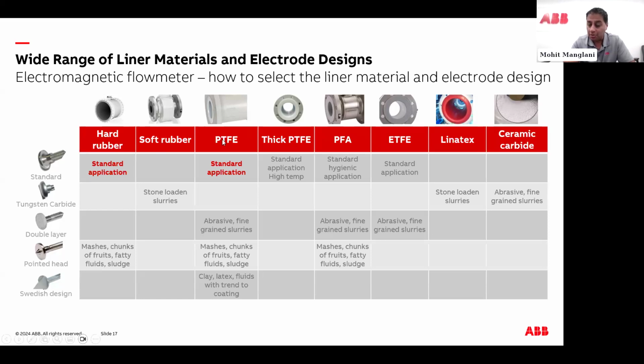You have Teflon. This is great for chemical applications, upstream, and oil and gas applications. Thick Teflon, which is basically Teflon but thicker, so it can handle higher temperatures. You have PFA, which is another type of Teflon. ETFE, which is the same as Teflon, except bonded. Linatex, which is a super soft rubber. And ceramic carbide for those super harsh solids applications, like in the cement market.